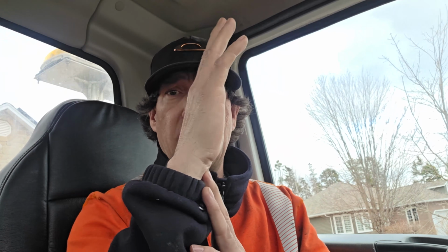So I closed it in. I always try to teach guys when they're using an extendo stick, don't stand directly below the switch, for 2 reasons. As the sections go down inside each other, there's a little bit of play, so when you have 6, 7 sections, whatever, and you're directly underneath, that wiggly stick gets really wiggly. So if you step back from the pole 10 feet or so and let it lean down, you have more control, plus you're not directly under the switch.